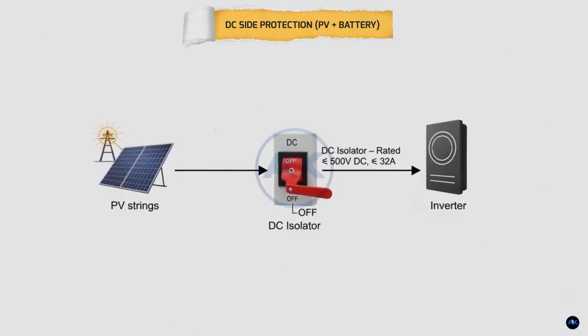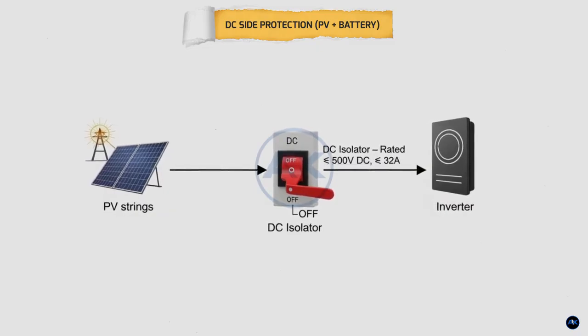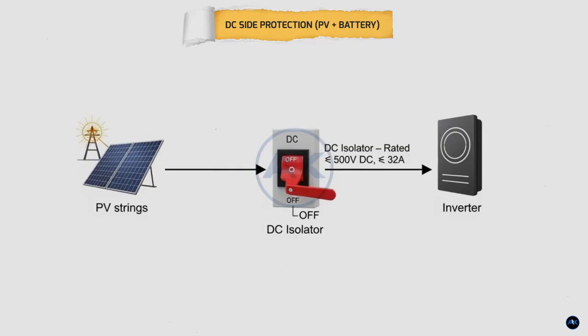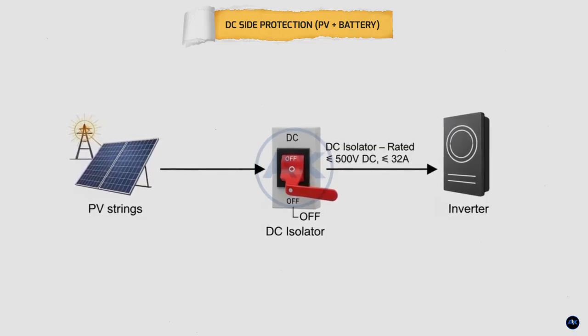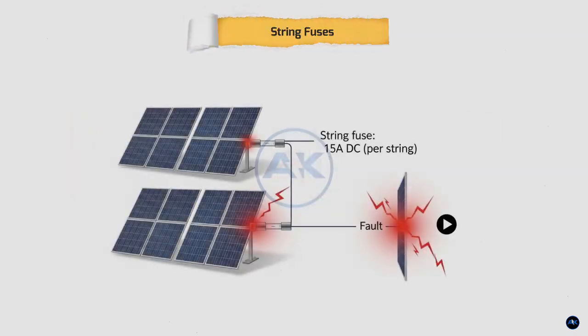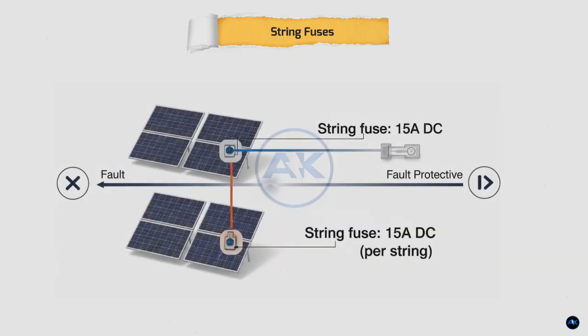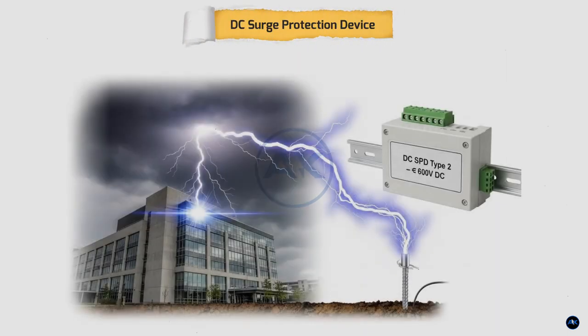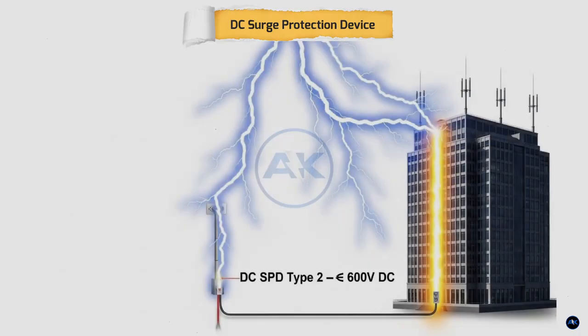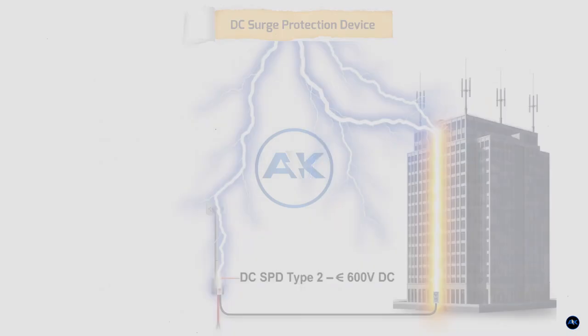DC isolators, PV side. Every solar system must have a DC isolator between the panels and the inverter. This allows you to safely disconnect the PV array for maintenance or emergencies. String fuses. Because we're using parallel strings, string fuses are mandatory. Each string must be protected individually to prevent reverse current during a fault. DC surge protection device, Type 2 SPD. DC surge protection protects your inverter from lightning-induced voltage spikes, even indirect ones. For rooftop systems, Type 2 DC SPD is the minimum requirement.